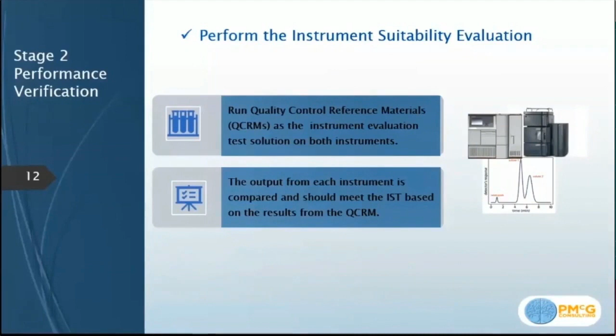After we have accommodated the control or the adjustment strategy, we're then ready to move to stage 2 of the lifecycle management and perform the instrument suitability evaluation. This is run using quality control reference materials as the instrument evaluation test solution on both instruments. We then compare the output from each instrument, and it should meet the IST based on the results obtained from running the QCRM.